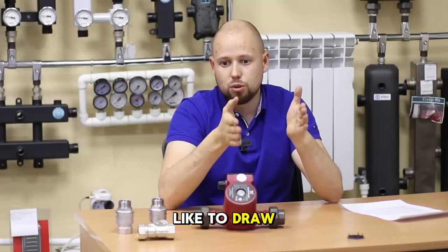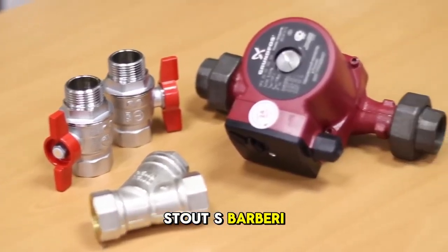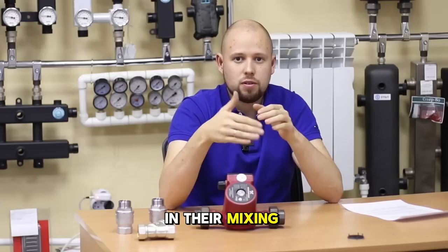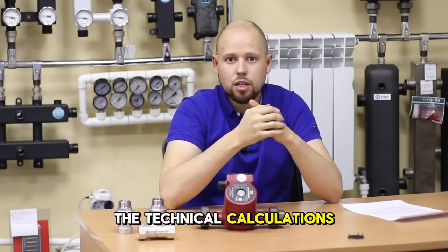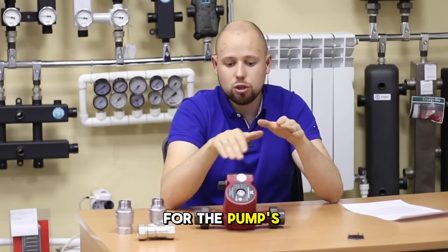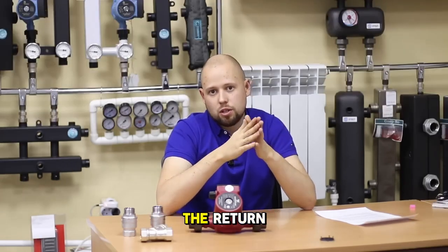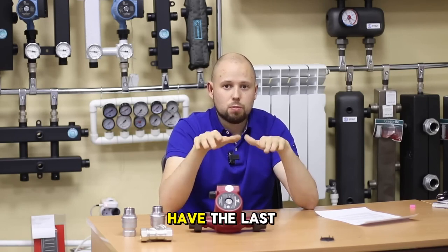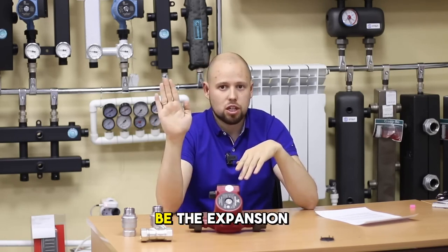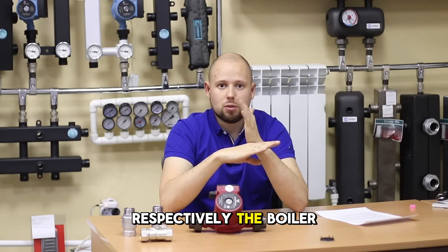I would also like to draw attention to the fact that many large companies, such as Meibes and Stout, install the circulation pump on the supply in their mixing groups. I think there are smart engineers there making all the technical calculations for the pump's service life. That said, I would still try to install it on the return if you have the opportunity and it is convenient. My preferred configuration would be: last radiator, then the expansion tank, then the circulation pump, and after the pump, the boiler.